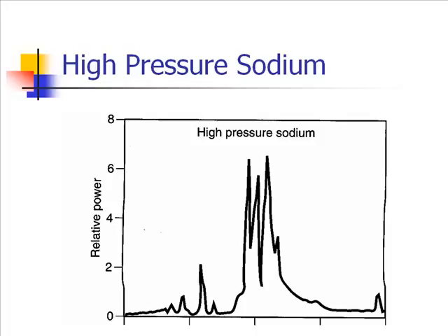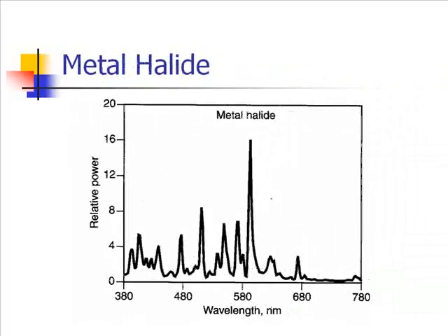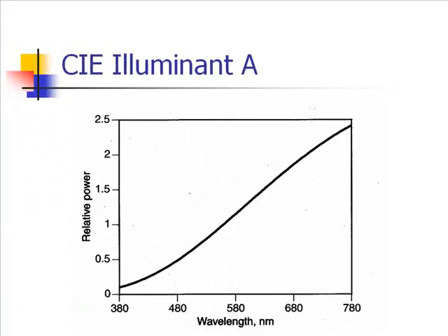Illuminant A. We'll talk about the CIE and what it does, but it specifies an illuminant A. This is that incandescent light, 2856 Kelvin light. It goes like that, and that shows the curve for that. And these are CIE illuminants, standard illuminants, if you will. D50 and D65 are the most common daylight equivalents that are used in light booths. The one we have in our light booth is D65, and that's this one here.